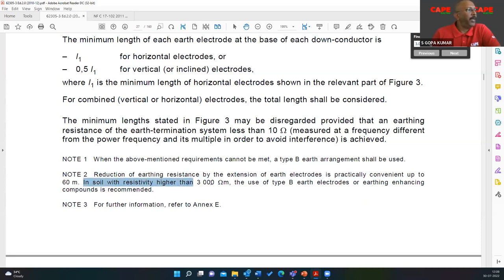In soil with the resistivity higher than 3000 ohm meter, see, the wording is very clear, the use of type B earth electrode or earth enhancing compound is recommended. So for more than 3000 ohm meter, two techniques are there: type B earth electrode or earth enhancing compound. Now practically in India, most places have soil resistivity of probably 100 ohm meter, 30 ohm meter, 50 ohm meter, 200 ohm meter. For that soil resistivity, of course, earth enhancing compound is not necessary, and earth enhancing compound will only accelerate the corrosion.